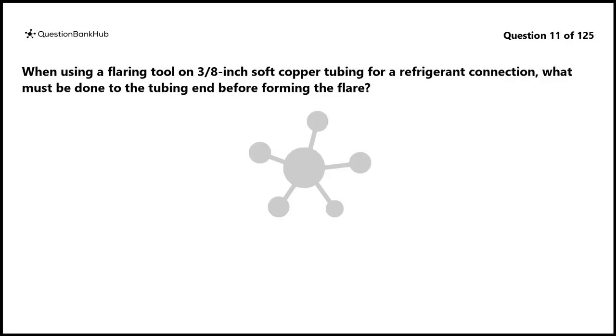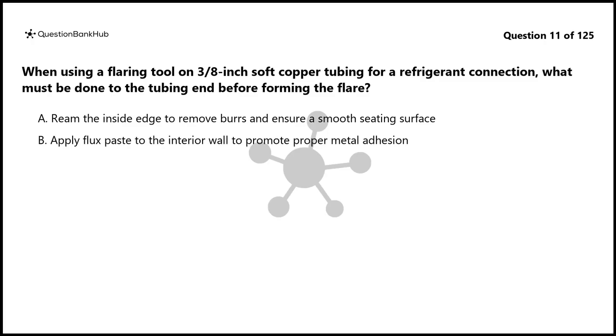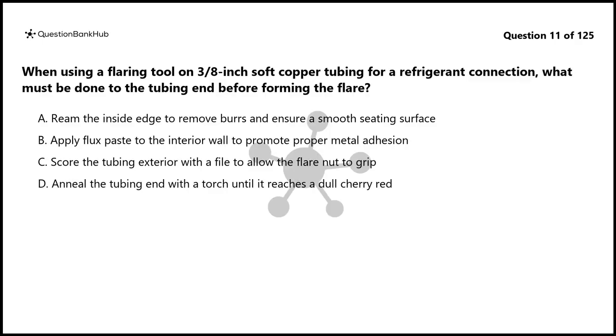Question 11. When using a flaring tool on 3/8" soft copper tubing for a refrigerant connection, what must be done to the tubing end before forming the flare? A. Ream the inside edge to remove burrs and ensure a smooth seating surface. B. Apply flux paste to the interior wall to promote proper metal adhesion. C. Score the tubing exterior with a file to allow the flare nut to grip. D. Anneal the tubing end with a torch until it reaches a dull cherry red.